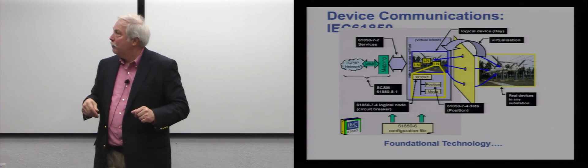61850 has this as a built-in function. So as a client, when I first connect to a relay or any IED - by the way, IED is not improvised explosive device, it's intelligent electronic device. We've been having a debate in the industry on how to change the name, but so far we haven't gone past IED yet. When I first communicate to the IED, I can say to it, who are you? In response, the IED will tell me all of the models it knows and all of the services it supports. So it can completely describe itself to me.